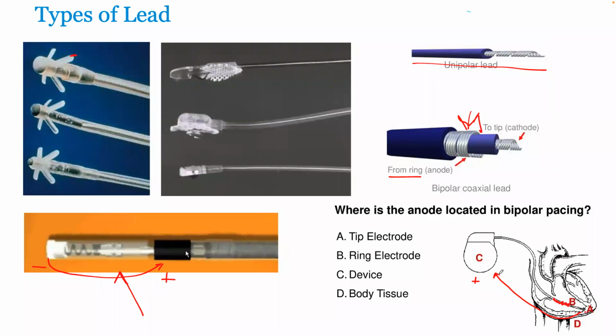So if you do find yourself finding patients with a high impedance in bipolar, an acute high impedance, then it's always worth testing it in unipolar. And if the unipolar is okay, as I said, you can pretty much then isolate the issue to the ring electrode. If you go to unipolar and the issue is still high, then the issue typically lies with the tip electrode. So you are probably looking at lead replacement at that point, almost imminently.